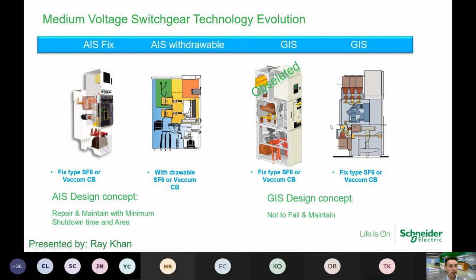And also we covered the GIS, the single bus bar and also the double bus bar design as well. So the double bus bar or the single bus bar design, generally for GIS, in short, is maintenance free and it's designed not to fail, all right? Because the high voltage components are all housed inside the SF6 gas. So in a way, which is a huge benefit for the clients in terms of the operating expense. All right, so the middle model, this one is our GM set. So the GM set has been obsolete in here. All right, so pretty much the focus that we have right now for the market is the GHA and also the GMA series.